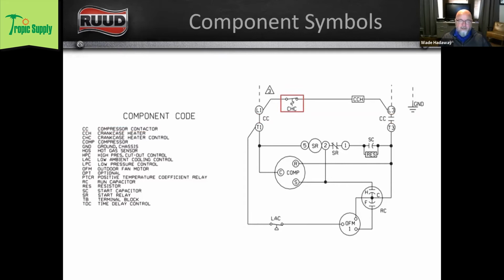We can also look at this schematic diagram, and we can see that we have some other switches, right? CHC is a crankcase heater control, and LAC is a low ambient control. Just from looking at the symbols themselves, you can tell what type of switches these are. On the crankcase heater control, on the top, you can see that red squiggly line, that designates that this is a temperature switch. So I know right away that the crankcase heater control is a thermostatic switch or a temperature switch. And I can also tell by the drawing that it opens on a rise in temperature.